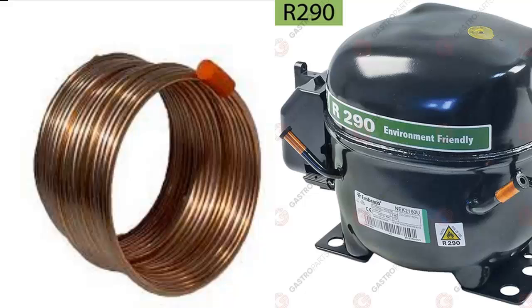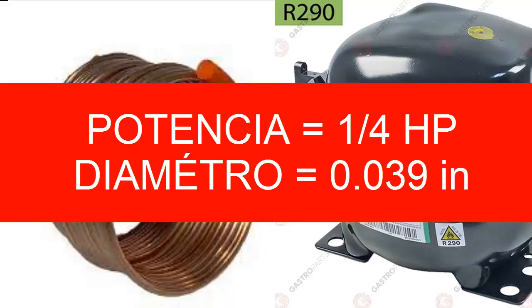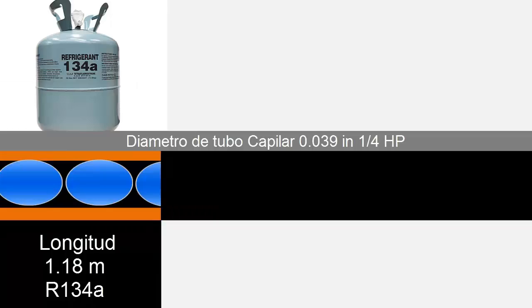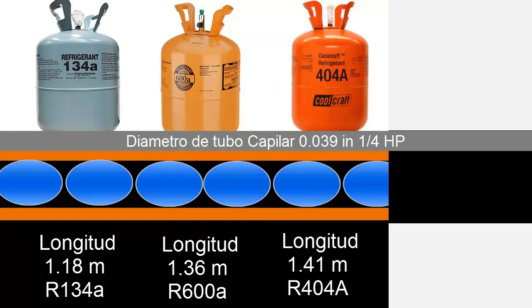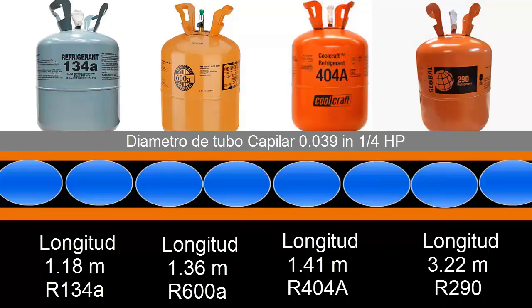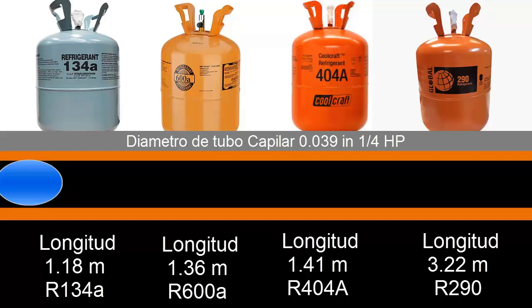Let's start with the first refrigerant: for R-134A the length of the capillary must be 1.18 meters. With this same diameter of 0.039 inches the length must be 1.36 meters when we work with R-600A. When we go to R-404A the length must be 1.41 meters, and when we work with R-290 the length of the capillary must be 3.22 meters.